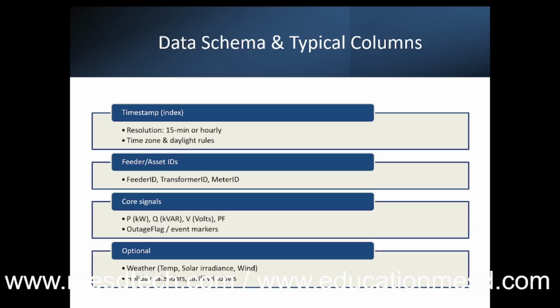At that time, for a few particular hours, they reduce the load in some areas, and that's only possible when you know your transformer ID, your feeder ID, and your meter ID. The transformer is connected to the main network, a feeder is connected to the transformer, and a meter is connected to the feeder. So if the meter load is low, the feeder will ask to reduce the load, the transformer reduces load, and the main power station will reduce the load on the main section.